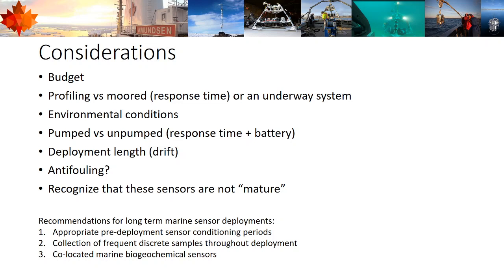Is it a profiling application or a moored application? If it's moored and it's sitting at the same depth throughout the entire deployment, then response time might not be so much of an issue. But if you're profiling and your sensor package is moving up and down the water column, then you're going to want something that's a little bit faster to capture that variability as your wave glider or Argo float or Rosette is moving through the water column.